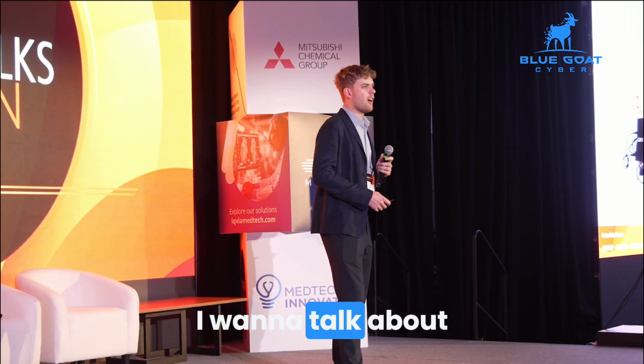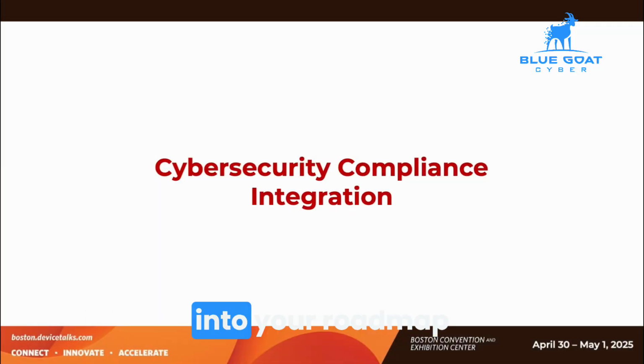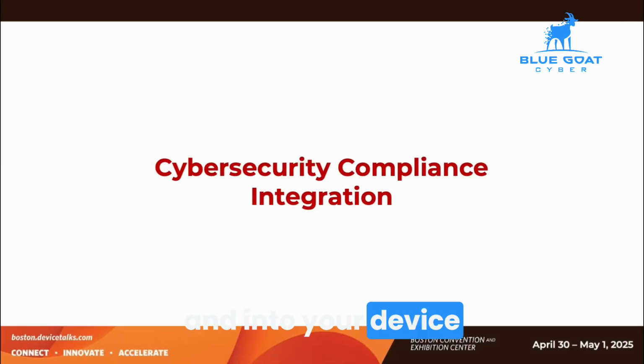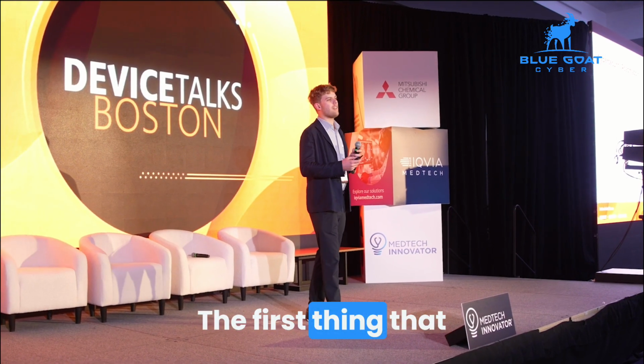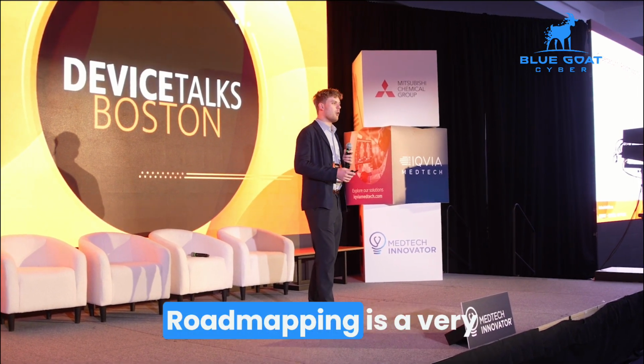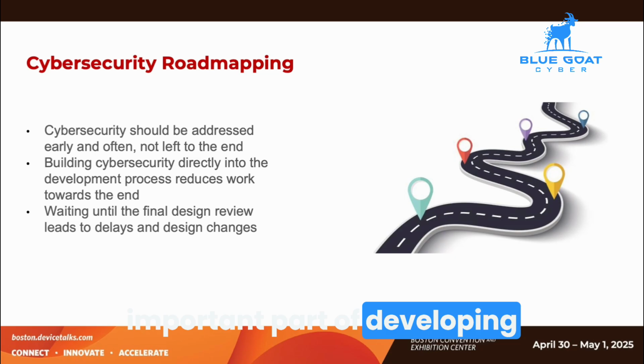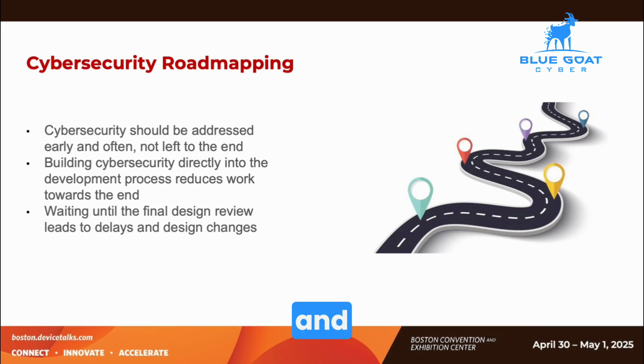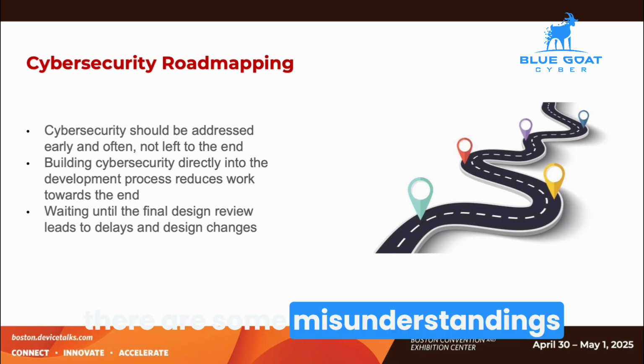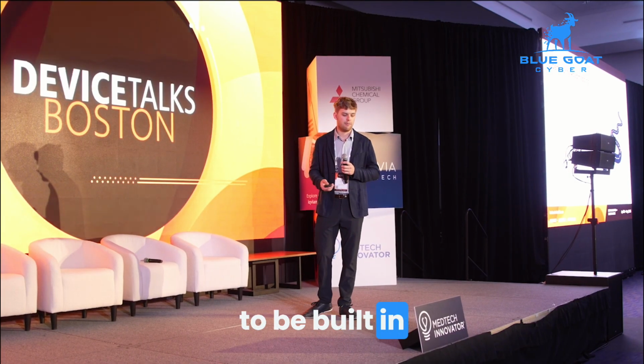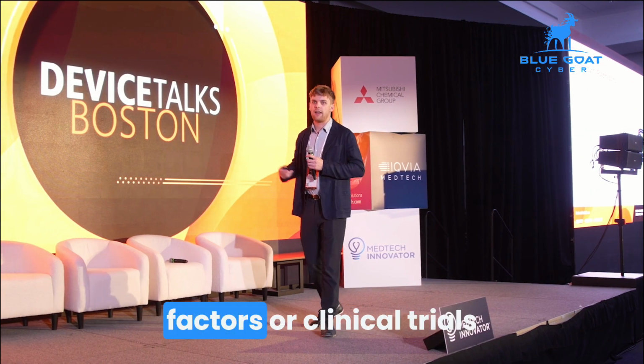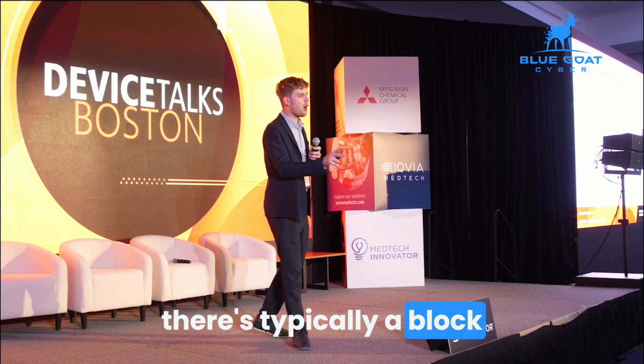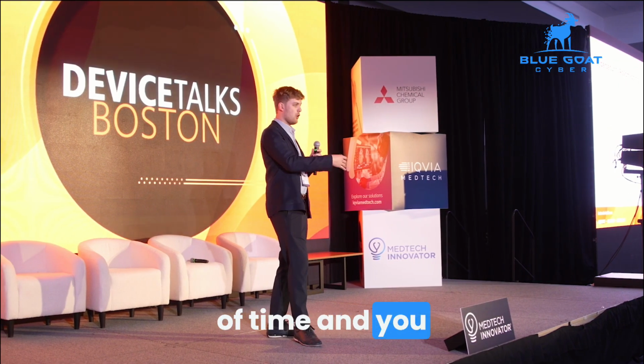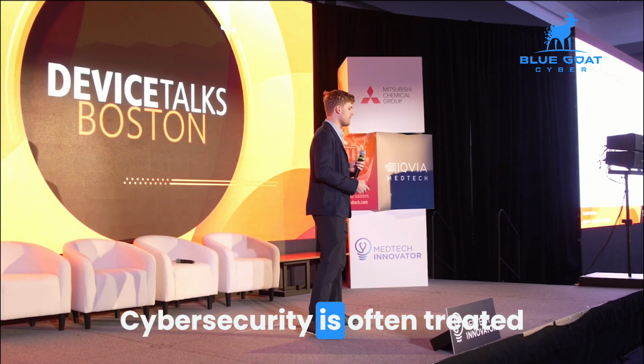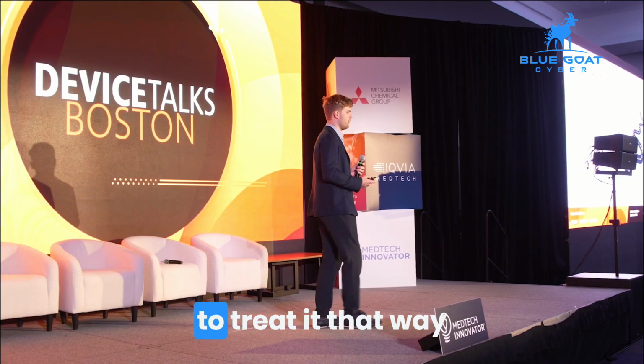Now, the first thing that I want to talk about is how we're properly integrating cybersecurity into your network, into your roadmap, and into your device, of course. The first thing that I want to talk about is road mapping. Road mapping is a very important part of developing a medical device, and a lot of times there are some misunderstandings on where cybersecurity needs to be built in. With something like human factors or clinical trials, there's typically a block where you do them. You pick a set of time and you go through the process. Cybersecurity is often treated the same way, but it's not effective to treat it that way.